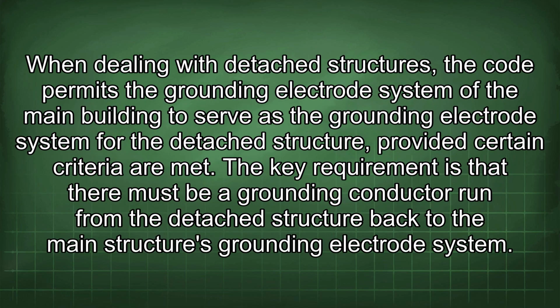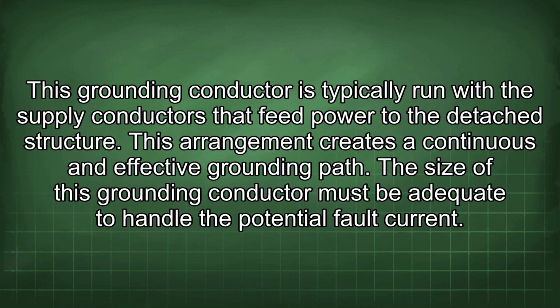When dealing with detached structures, the code permits the grounding electrode system of the main building to serve as the grounding electrode system for the detached structure, provided certain criteria are met. The key requirement is that there must be a grounding conductor run from the detached structure back to the main structure's grounding electrode system. This grounding conductor is typically run with the supply conductors that feed power to the detached structure. This arrangement creates a continuous and effective grounding path.